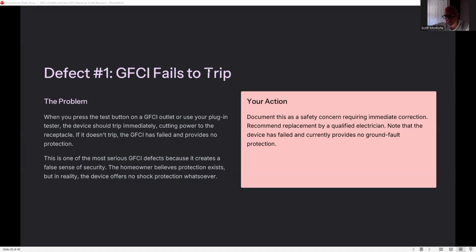Well, yeah, but the other problem with that, Scott, was that there are outlets we test that aren't GFI, but on a GFI circuit. Correct. Like your kitchen, it doesn't have a GFI push button. You test it with that push button, and it trips something somewhere, or multiples. And that's what the insurance company was getting at. They're saying, well, you go in the kitchen and sometimes you trip it, and here's the thing, just to show you the reason why I still use the tester. This is me. I've been doing it and I haven't had a problem.